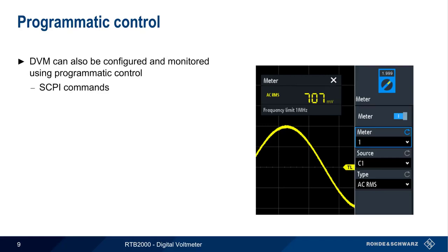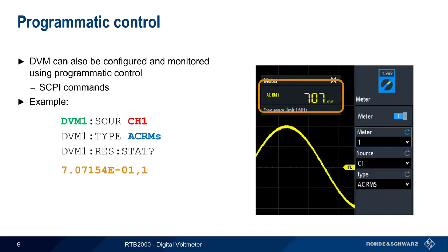The RTB2000's DVM functionality can also be configured and monitored using programmatic control, more specifically by means of industry-standard SCPI commands. For example, we could send this command to the RTB to assign meter 1 to channel 1. Another command could be used to change the meter type to AC RMS. A third command could then be sent to query the measured value, which is then returned in scientific notation. In this presentation, we won't get into details of programmatic control, so please see the RTB user manual for examples and a complete programming reference.